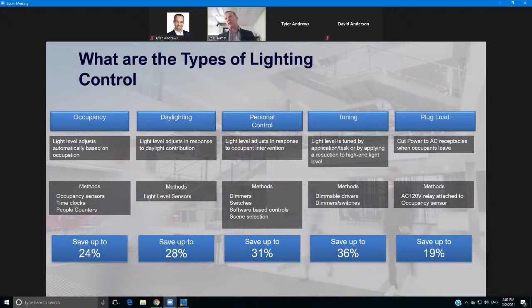Another form is personal controls—everything from a wall switch to personal choices. I know people with 2-3 monitors who don't want overhead lights on; for example, I have plenty of lights over my head but don't like them on when looking at screens. As for tuning, a dirty little secret: on most sites I commission, I actually set the top level at 70%, so right off the bat we save 30% off most building operating costs just by trimming it to 70%.